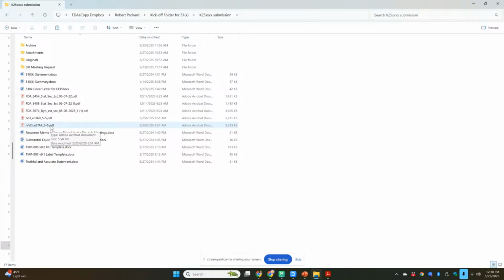So I copy and paste that from their instruction for use into my table, and then I try to look for the same things in our draft instruction for use, and I populate it. Now, some of the things in our instruction for use might change because we might not be quite finished with the IFU. We might not be quite finished with the design. So things might change, but at least I want to get everything down there for the predicate device right from the start.